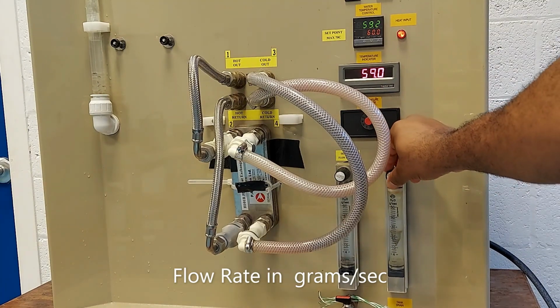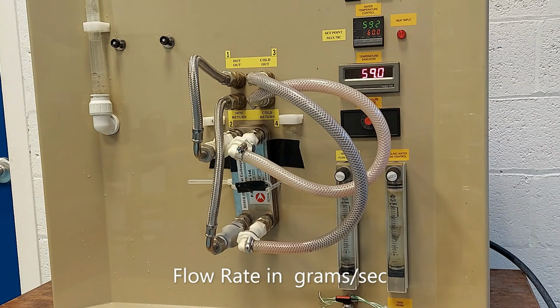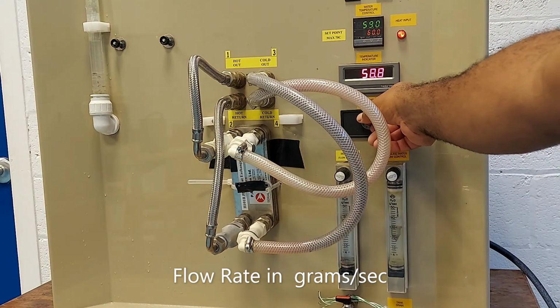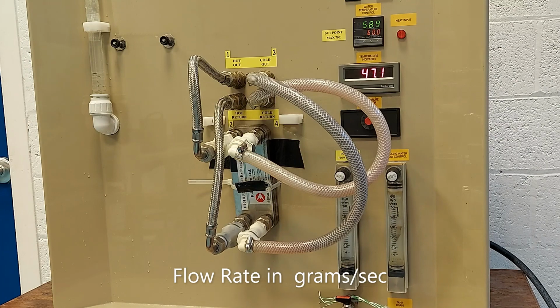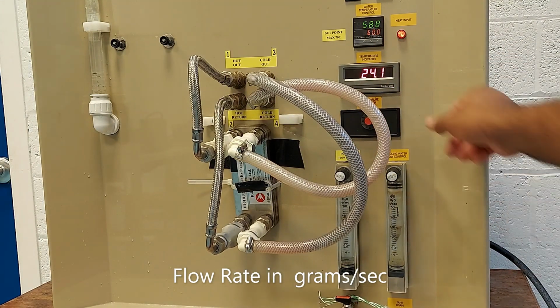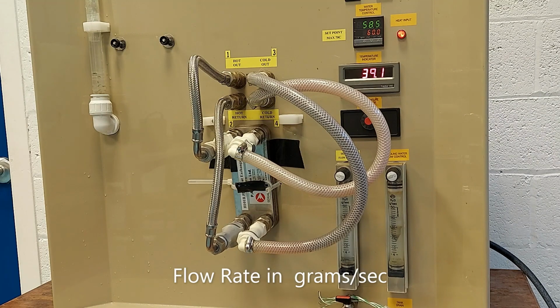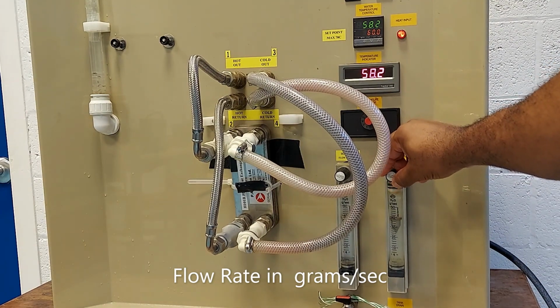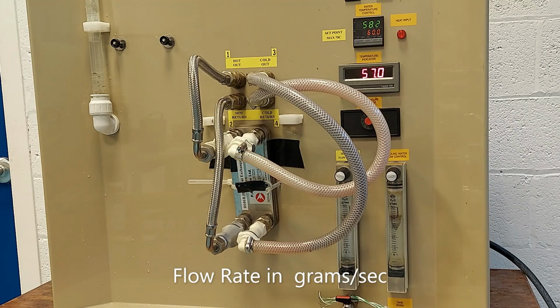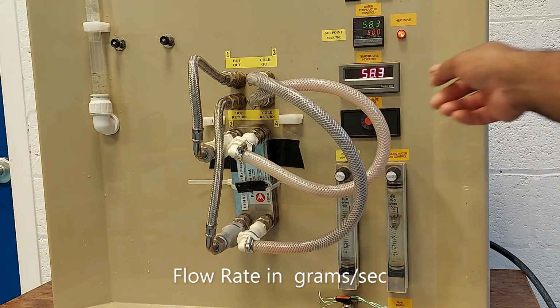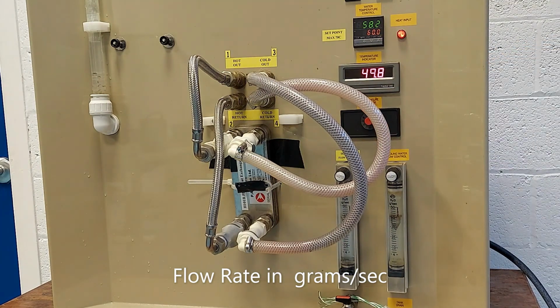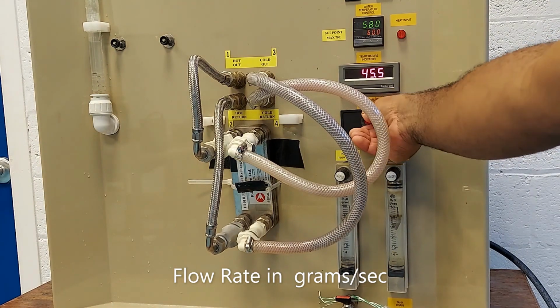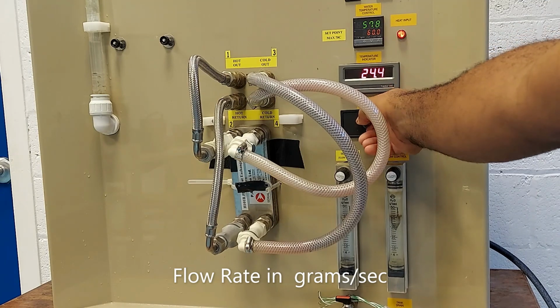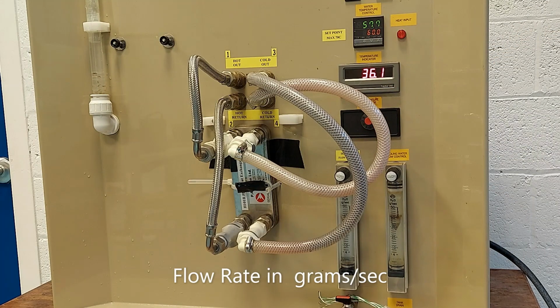We would then adjust our cold flow rate to 30 grams per second, allow for steady state equilibrium. Then we would take T readings: T1 58.8, T2 47.1, T3 24, and T4 39.1. Finally, we would take our flow up to 40 grams per second, and of course allow for steady state. Then we would observe our T readings. T1 58.2, T2 45.5, T3 24.5, and T4 36.1.